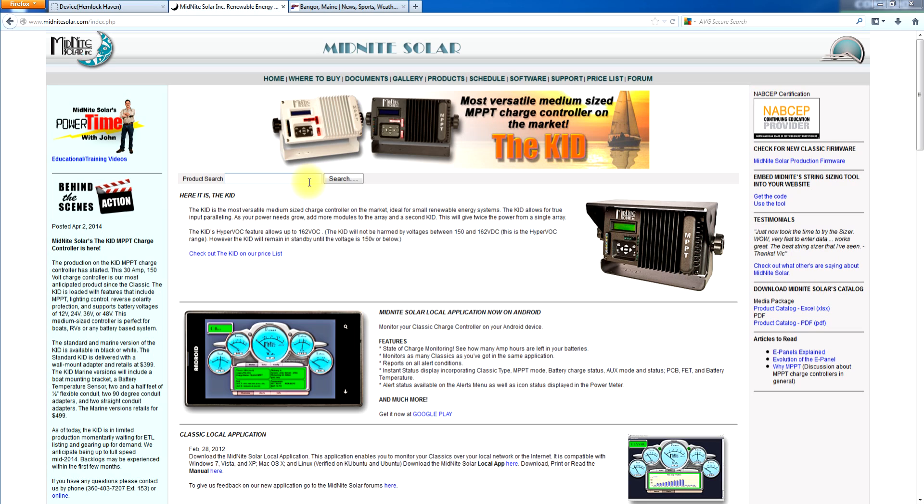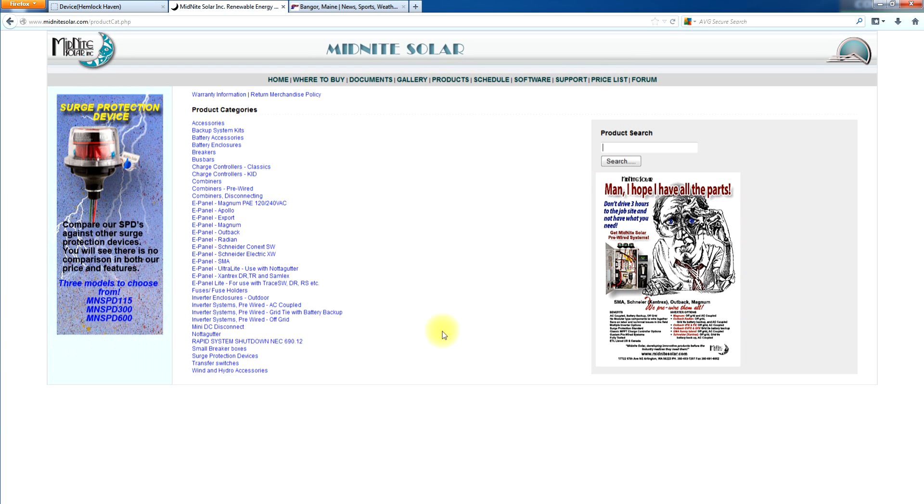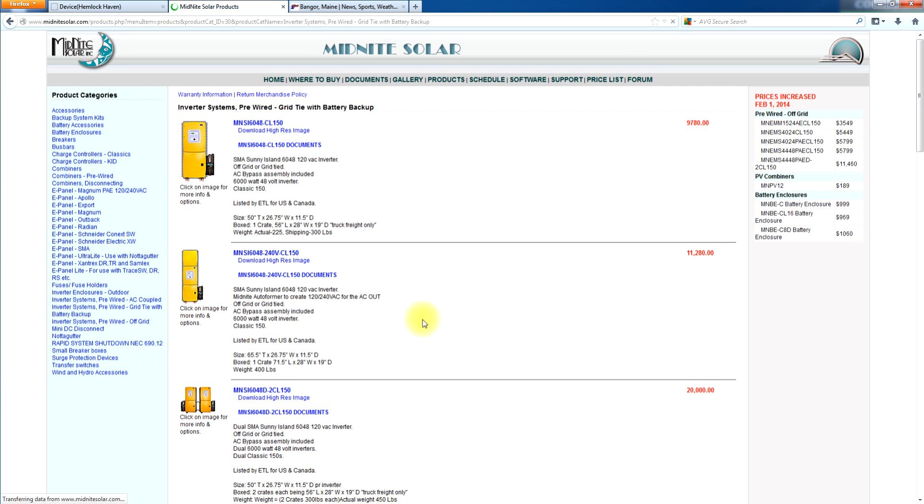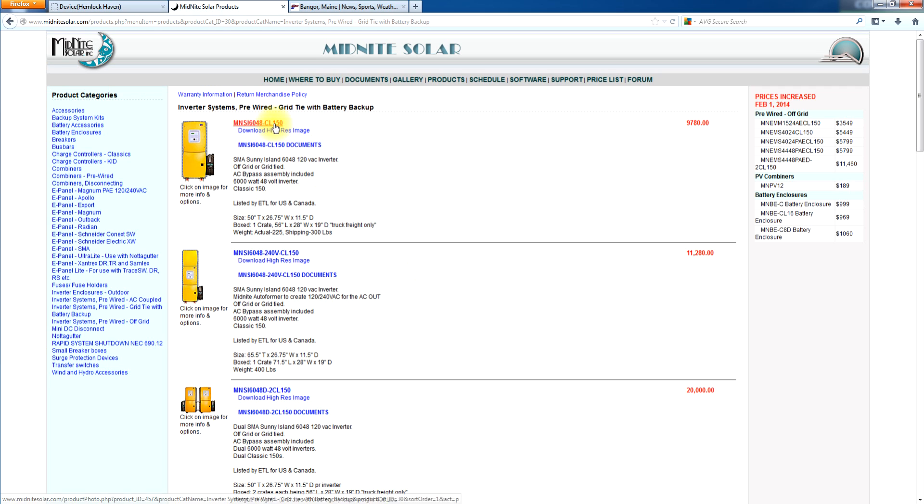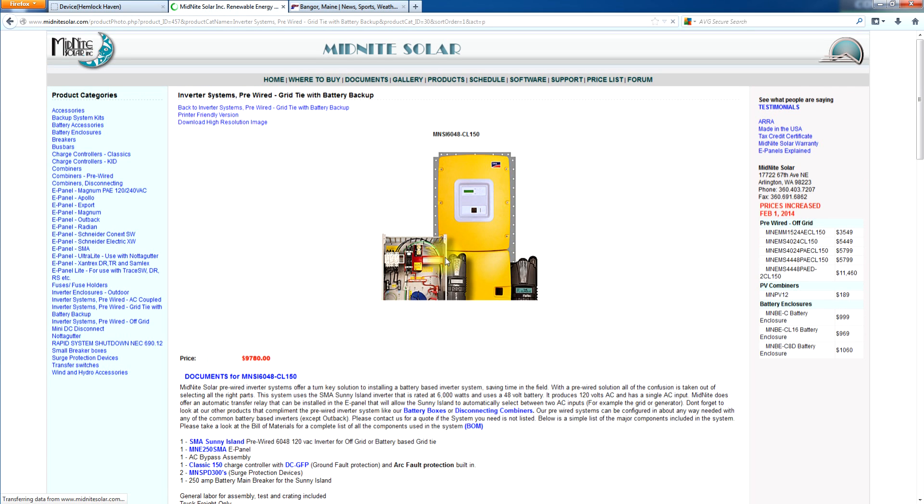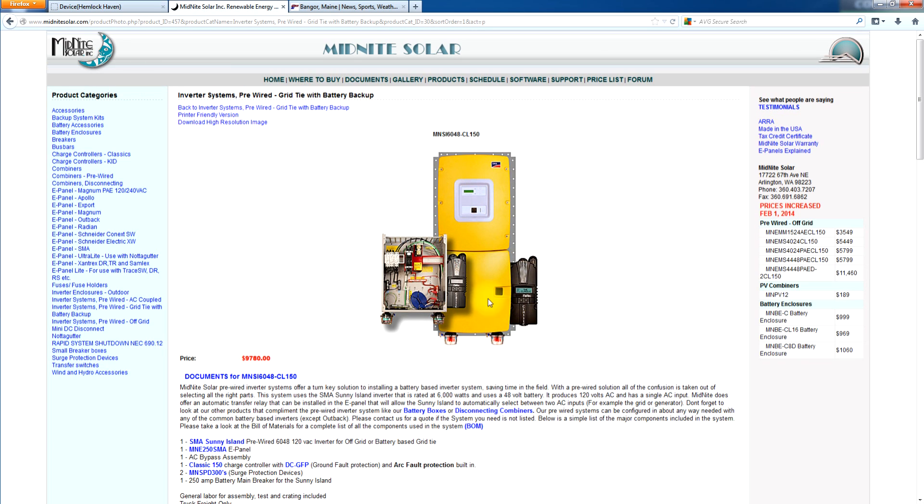We have a full line of accessories for the Sunny Island. The first thing I want to show you is some of the uses of Sunny Island, because one of the common things that people don't know is that the Sunny Island is a grid tie inverter. A lot of people think they have to have a Sunny Boy to make it grid tie, but that's actually not correct. So as you see here, we can do a single Sunny Island for 120 volts. It is 6KW and we can put classic charge controllers on it and we can make that grid tie or we can make it off-grid.